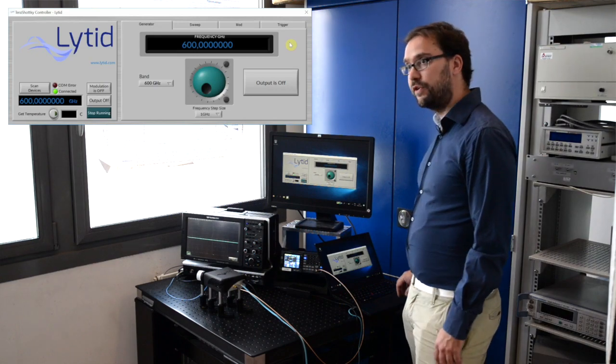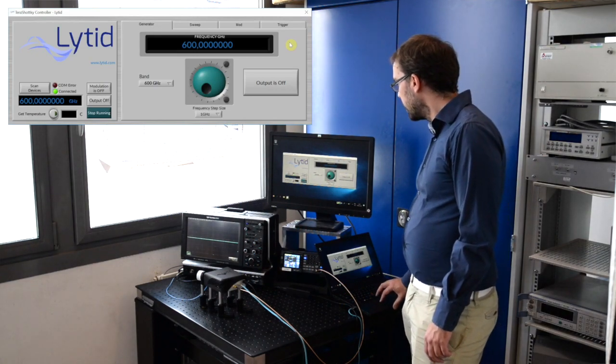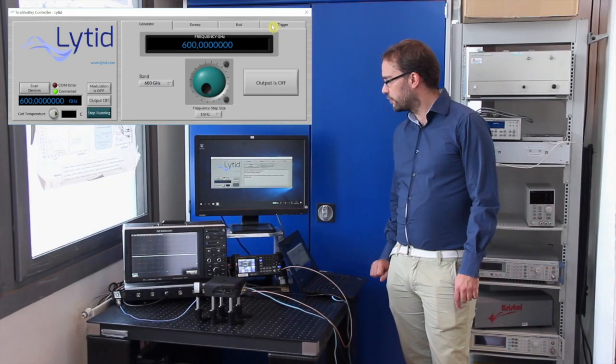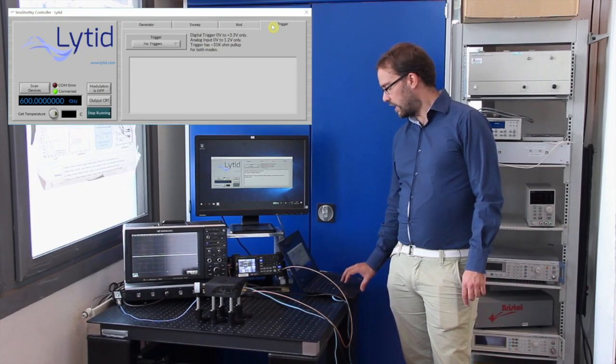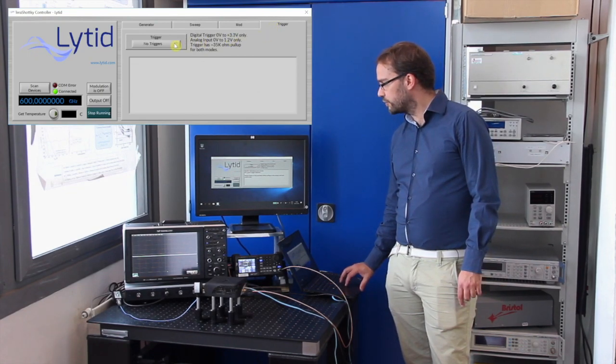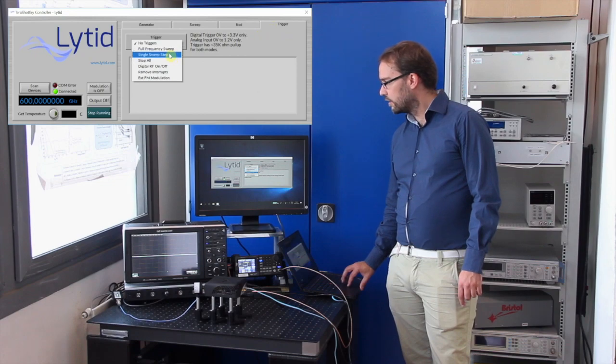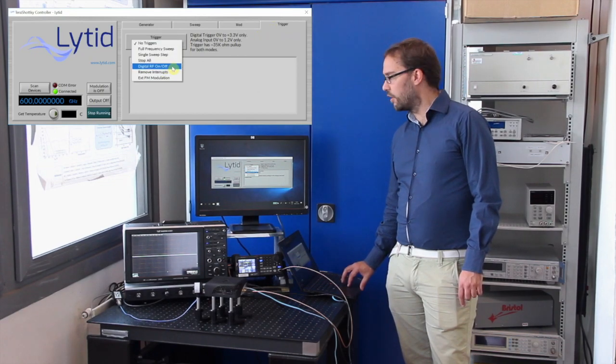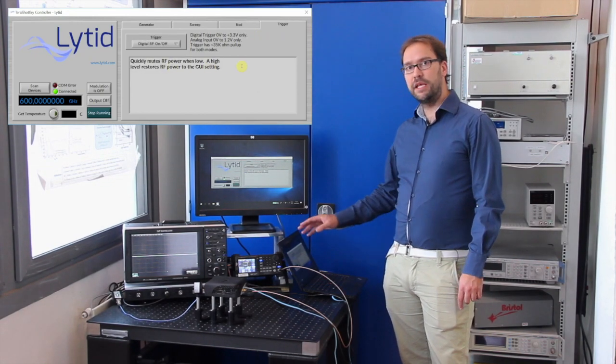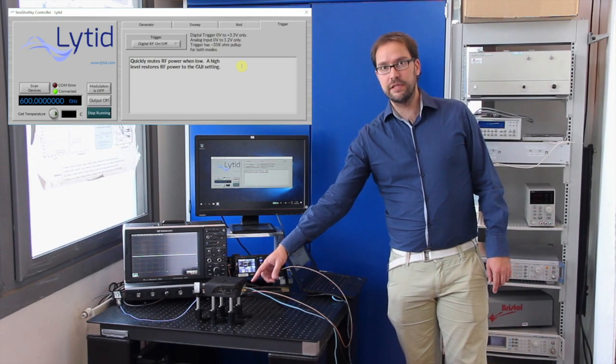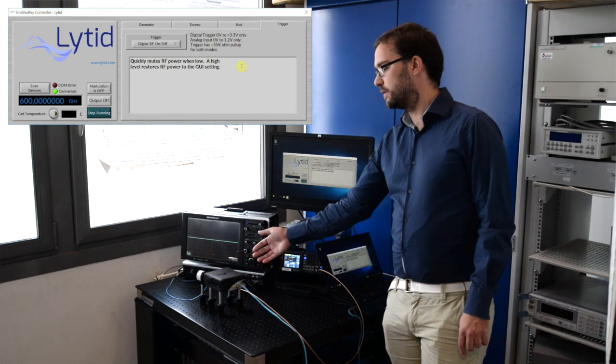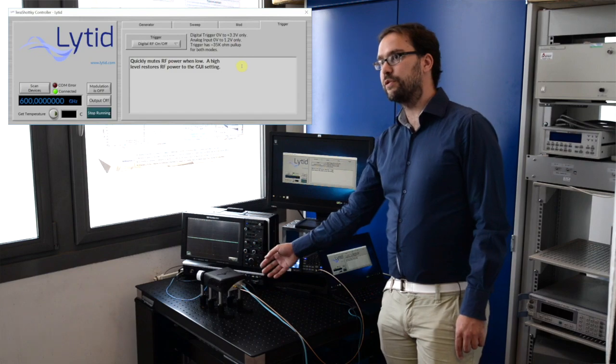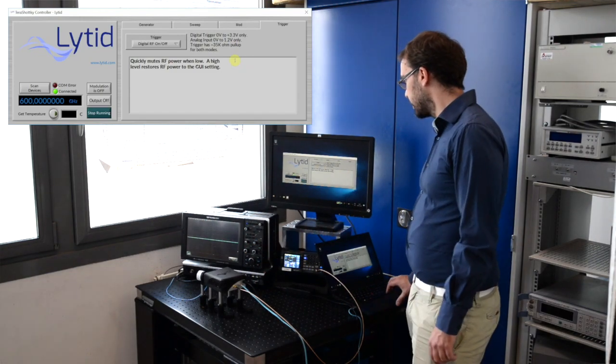To configure the software to use the external trigger, I will go to the trigger tab here. I will select of the triggers here digital RF on-off, meaning that on this pin when the signal is high the source will emit and when the signal is low the source will be muted. So let's try this out.